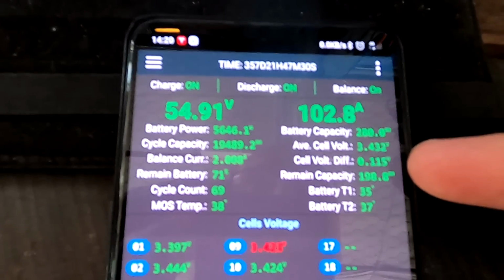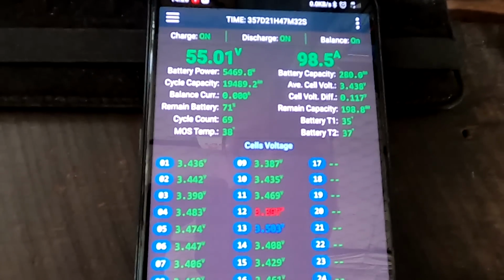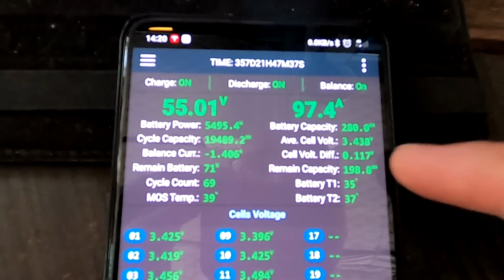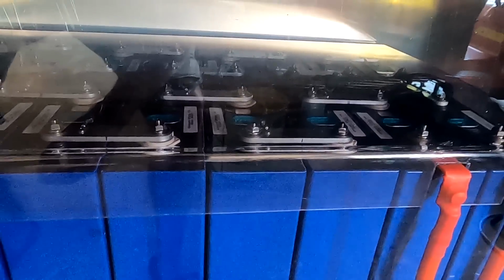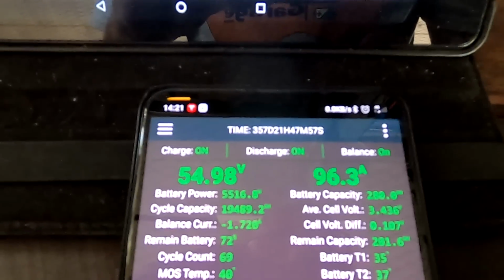We've got 115 millivolt here. Look at this. That is quite high actually. That is too high. So we need to have a closer look at the middle battery here with the aluminium bus bars and see what's going on. Maybe measure the internal resistance of the batteries, including the bus bars, to find any connection issues between bus bar and terminal of the batteries. So 100 millivolt deviation is a bit too much.